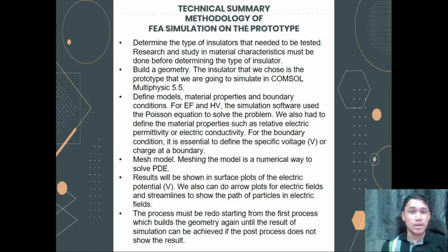In this project, a 132 kV system voltage glass string with a cap and pin insulator on industrial polluted areas is our focus. The load for this study is 175 mm² AAAC that has a weight of 659 per meter. For the material properties, based on the glass material, the value of relative electric permittivity is 4.2 and the value of electric conductivity is 0. The standard and data profile of the glass string insulator also must be studied.